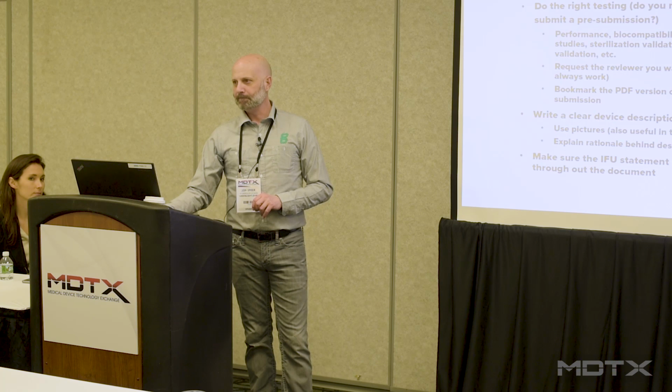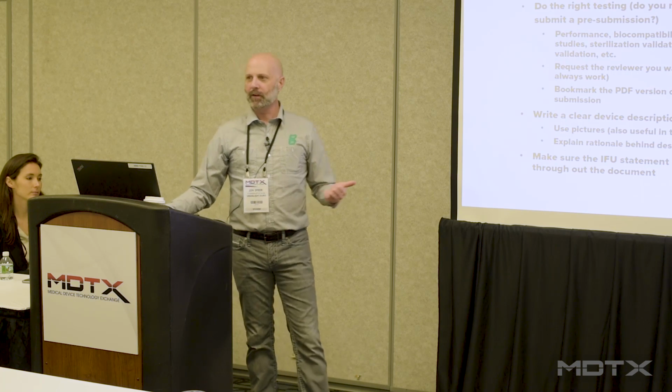A few tips. We talked about the I promise pieces earlier. If your product has patient contact materials and components, know about biocompatibility, and more importantly, do the proper biocompatibility testing for those materials. Corroborate it, do the risk assessment, and leverage experts in biocompatibility if you want to build that case as to why. If you have an electronic device, guess what? IEC 60601 is testing to that standard. It's going to be an expected behavior. So do yourself a favor and do that before you do submission.